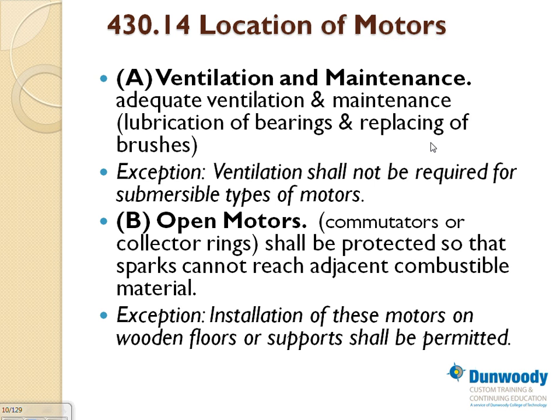Open motors. If you have open motors, guys, and these are DC, the collector rings, that doesn't ring a bell for you. If you have an induction motor in an air handling unit, you're not going to have collector rings and commutators. These DC motors should be protected so that the sparks cannot reach adjacent combustible material. The last thing you want to do is have a DC motor right next to something that could be ignited, and every time the brushes spark, you're going to ignite the surroundings. Take this, installation of these motors on wooden floor or support shall be permitted though.